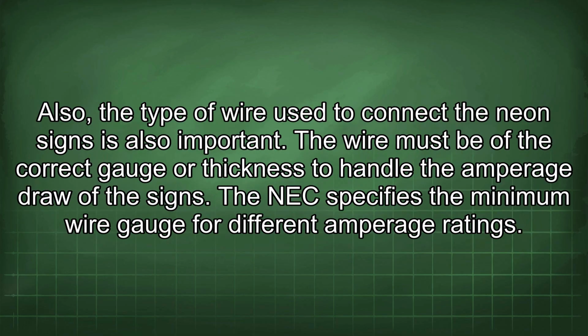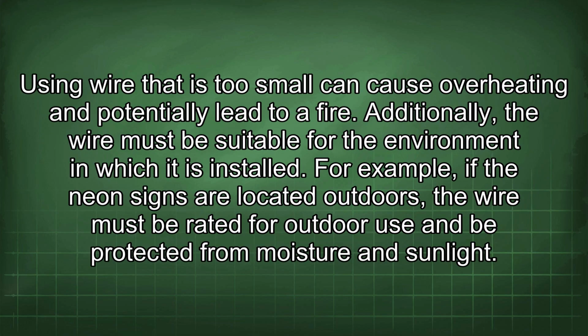Also, the type of wire used to connect the neon signs is also important. The wire must be of the correct gauge or thickness to handle the amperage draw of the signs. The NEC specifies the minimum wire gauge for different amperage ratings. Using wire that is too small can cause overheating and potentially lead to a fire. Additionally, the wire must be suitable for the environment in which it is installed.